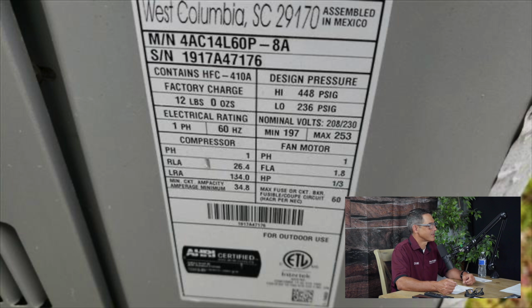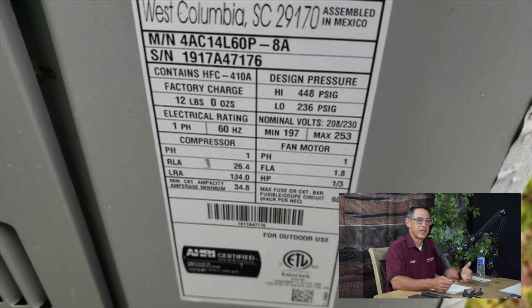Yeah, and the labeling on the condenser will actually dictate what the range is, right? Yeah. And it can tell you what size wiring you can use, which could be different than what's in the standard electrical code. Yep. So you have to read your labels if you're an inspector and check. Sometimes it will tell you what wire gauge is rated for that condenser, and then it will also tell you what breaker range you can have. And so it's not just read electrical code and cookie cutter for that. These condensers have different ratings, and there's exceptions.